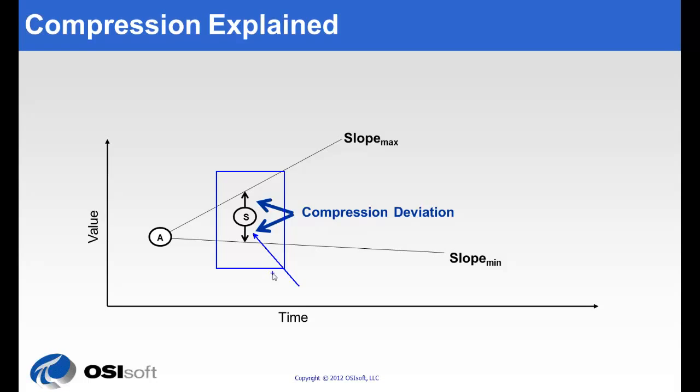As time goes on, it's entirely possible that this snapshot won't be needed in the PI archive. The first step is to calculate these slopes. We have an archive value, a snapshot value, the compression deviation settings, and we'll calculate the maximum slope and the minimum slope. A reference slope is calculated using the incoming event and compared to the maximum slope and the minimum slope. Then we have a decision to make.